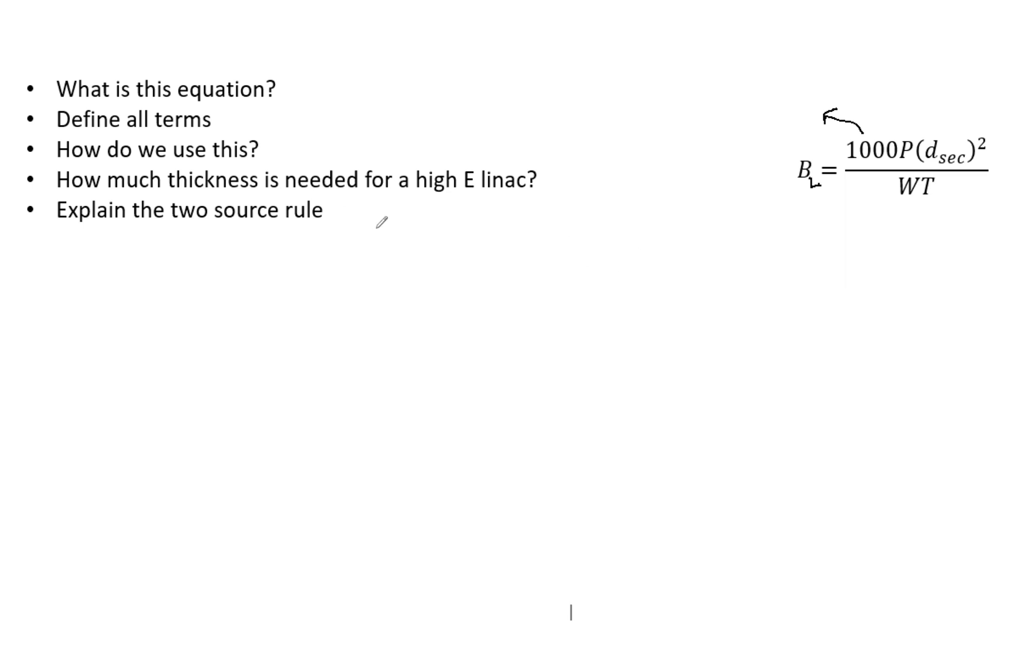So now how do we use this? Essentially, what we're going to do is we're going to calculate the transmission factor for leakage. Then we're going to calculate the transmission factor for the patient scatter. And then you are going to combine these using the two source rule. So ultimately, this is finding the secondary barrier.